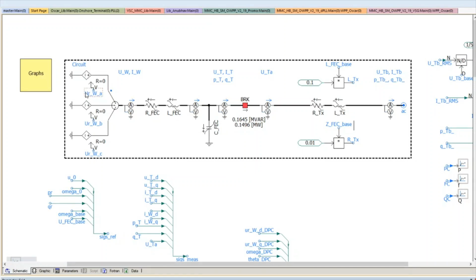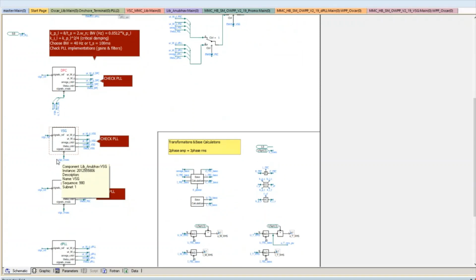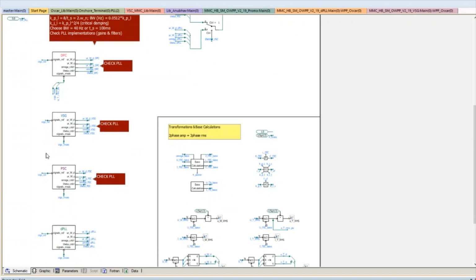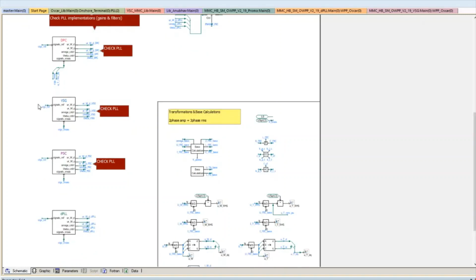The reference for the voltage source is generated by the control. We can have grid following controls or grid forming controls. Right now, because the purpose of this work is to look into energization capabilities and islanded operation of the wind turbine, we studied grid forming controls. And right now we have implemented 4 different controls, namely the direct power control, the virtual synchronous machine control, power synchronization control, and the distributed PLL. However, these can be enhanced, and more controls like the synchroconverter and other VSM based controls can of course be added.